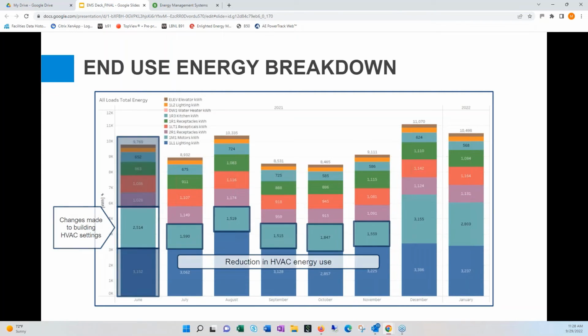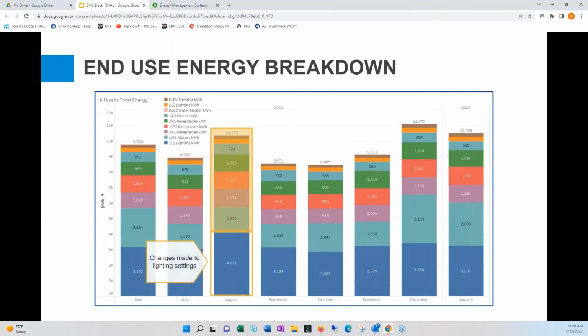Moving on to the lighting system, we made a change not until August here, but what we found was that there's a lot of lighting in this library, and a lot of it was more decorative than for reading or real purpose. Yet all of the lighting was set the same way, basically to the max output of the fixtures. So we were able to identify a large amount of lighting fixtures that didn't need to be at full output.